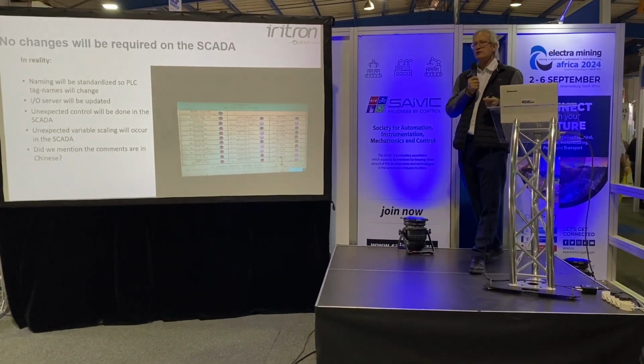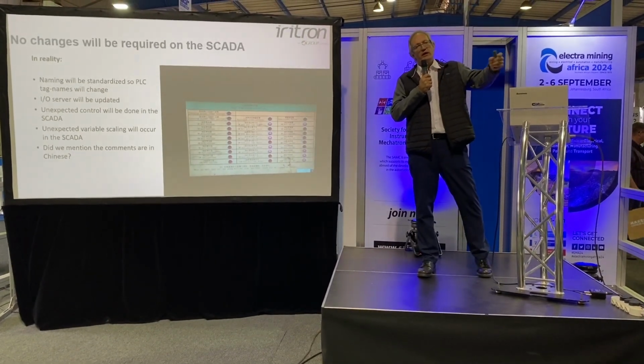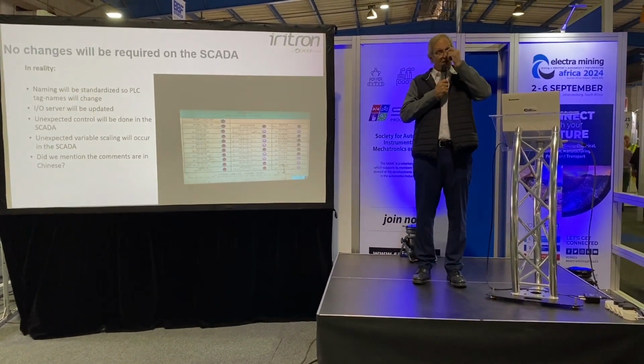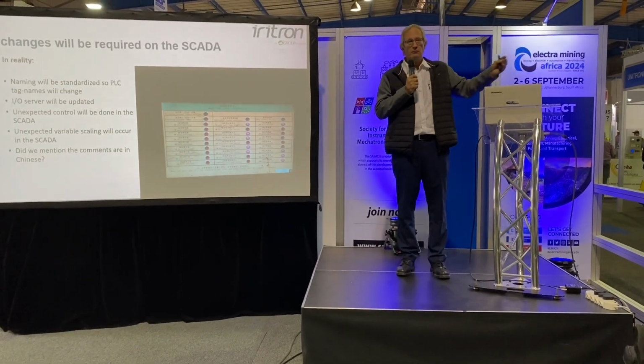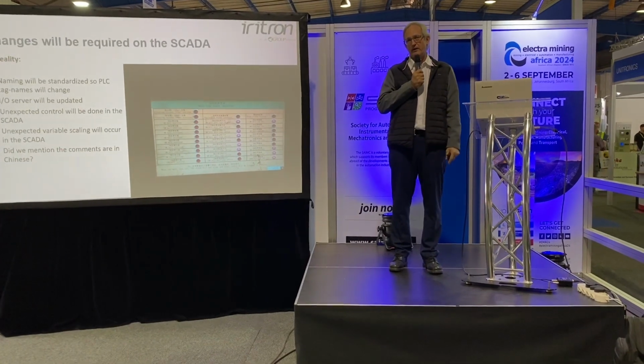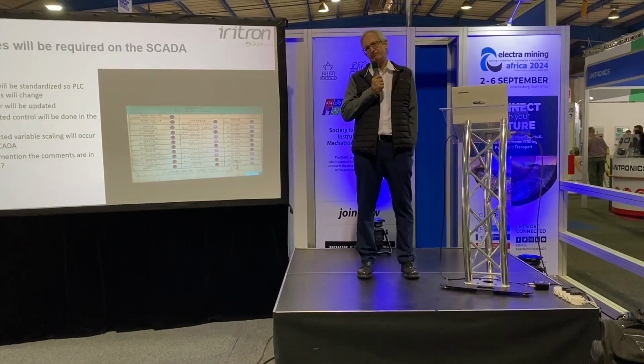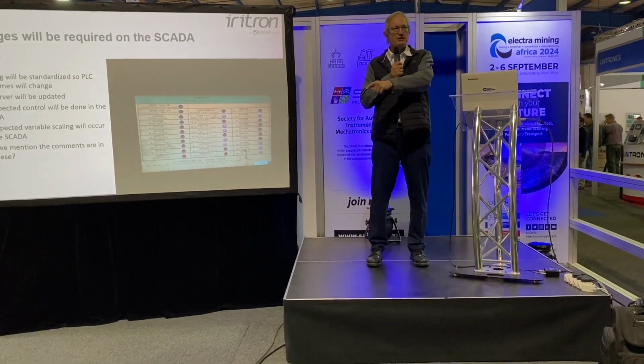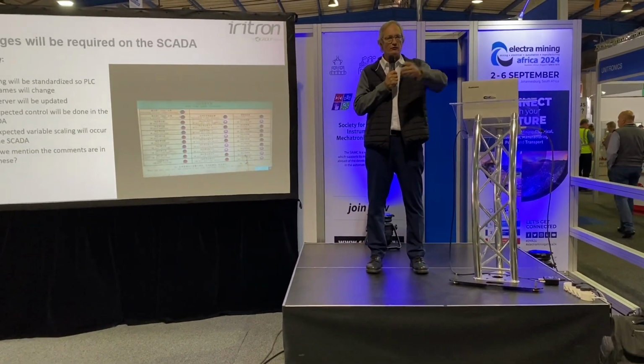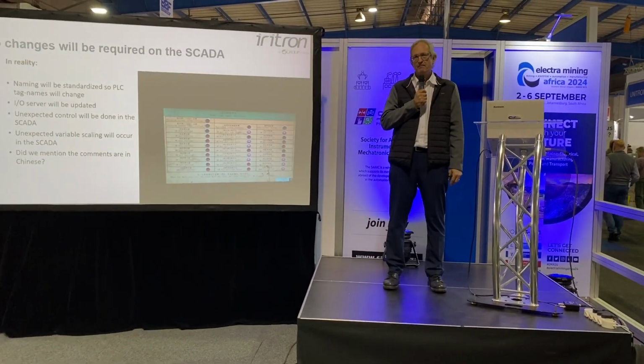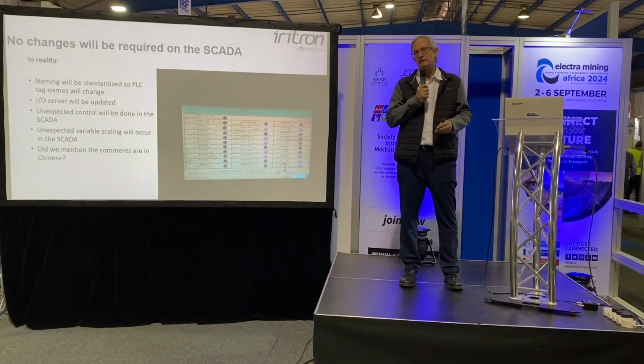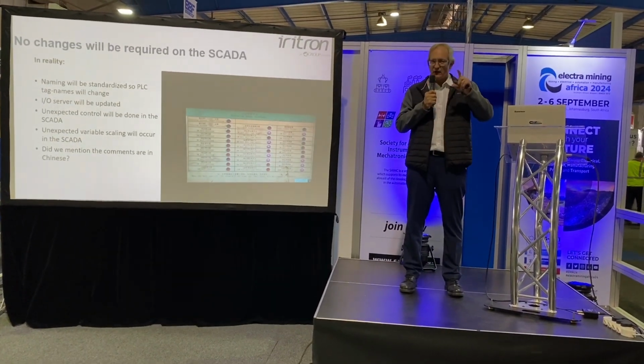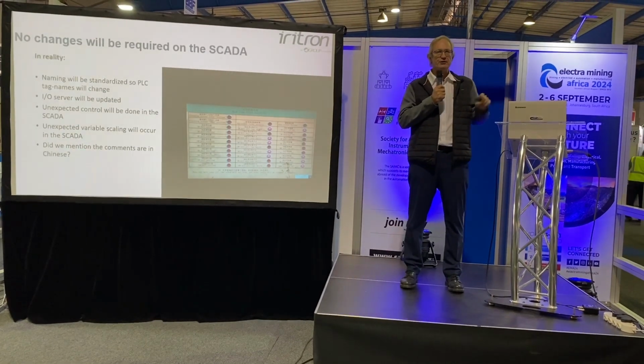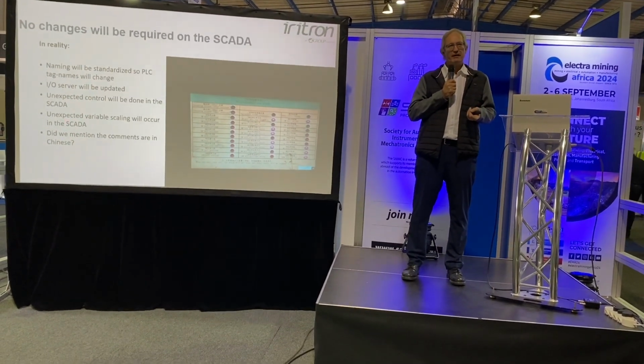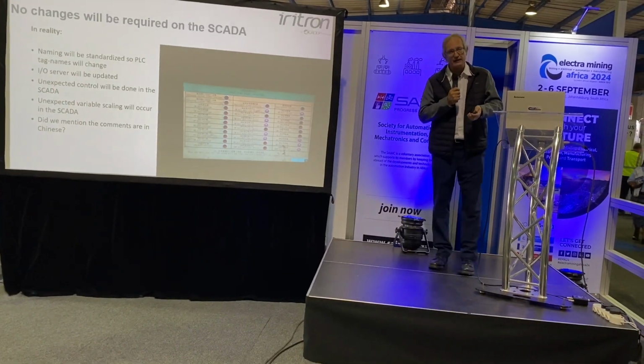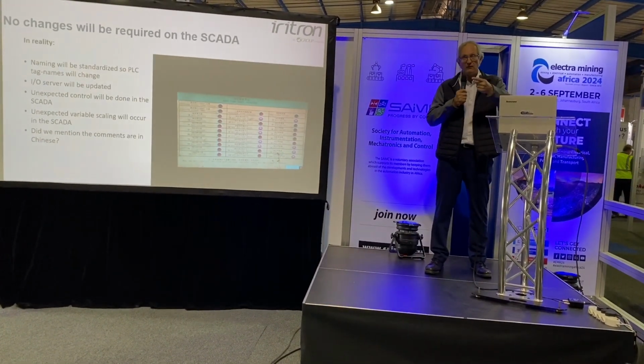And then you'll find during commissioning that when they did the initial commissioning of this plant, after they've sent the PLC guy home, there was some additional control that had to be done. So we scripted that into the SCADA. We didn't tell anybody, but we scripted it into the SCADA. So when you upgrade your control system and it's not part of your control philosophy, when you put in your new SCADA, then you don't put in that script, because control does not belong in the SCADA. Control belongs in the PLC. And then the plant doesn't work. And then you have to go back to the SCADA and investigate and analyze all the scripts to see what has changed.